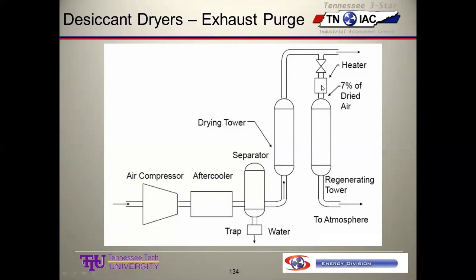Typically, these are electric resistance, which is expensive energy. It can be hot air. It could be steam. It could be a waste heat source, which would be really nice, which would reduce the cost of operation. But I'd say 90% of the time, this is just good old strip heaters, which are pulling electric energy and heating this compressed air before it regens the tower. If you get it hot enough, nominally 250 degrees or above, that's a fair amount of heat, you don't need as much. So you need roughly half.